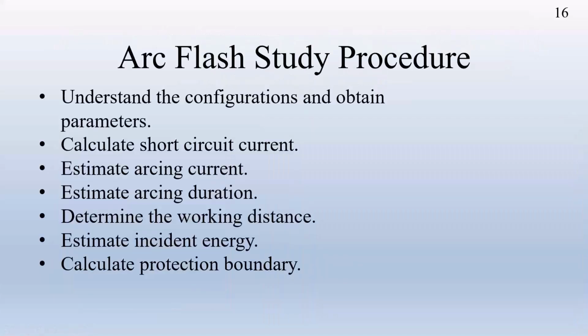And of course, when you look at the arc flash study procedure, everybody knows that. You understand the configuration and obtain the parameters, calculate your short circuit current, and then estimate the arcing current. From the arcing current, you estimate the arcing duration. When you use EasyPower, it helps you do all this because it has a table of fuse curves or relay curves, so you can estimate the arc duration. Then you determine the working distance, normally the distance from the arc initiation point to the worker's chest area. Then you estimate the incident energy, and then you calculate the protection boundary, which of course is based on 1.2 cal per centimeter squared.